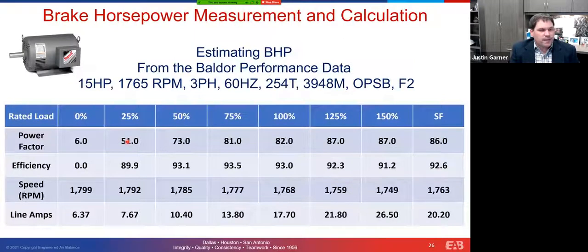So this is data from a manufacturer, from Baldor, for this particular 15 horsepower motor. We're gonna use this in the coming example. But you'll notice here at 0% load, we have a power factor of 6 and an efficiency of 0. And we don't really care about the speed at this point, but you'll notice that the speed does change. But our amperage here is 6.37 amps. Whereas if we jump over here to 100% load, obviously you can see our power factor and our efficiency have changed. And our amperage now is 17.7. So this formula that we're talking about, and really that L factor, is trying to help us bridge the gap between this number and this number right here when we start talking about percent loading.